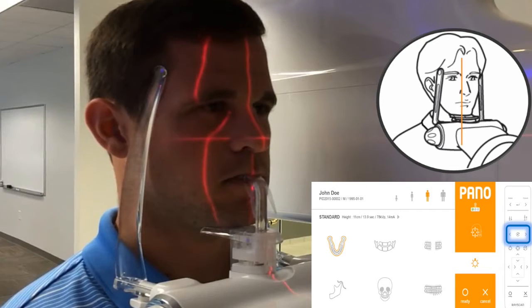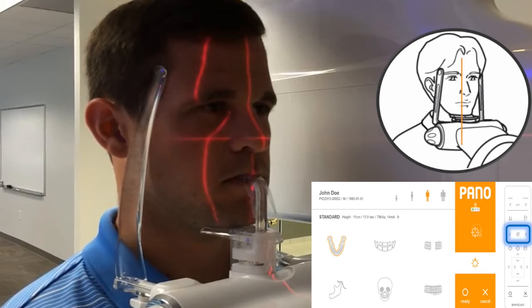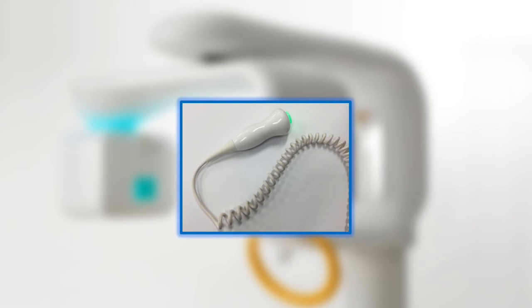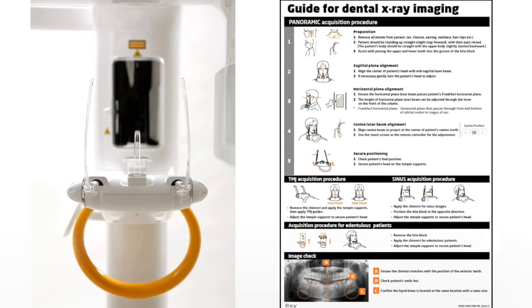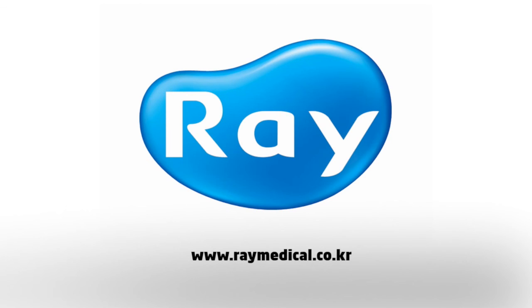Carefully adjust the head supports so that they gently but firmly grip the patient's head. Ask the patient to maintain a firm grip on the hand grips and step forward slightly. This position makes them slightly off balance and hanging onto the support handle, forcing them to stretch their neck as far as possible, which decreases the spinal shadow on the anterior regions. Ask the patient to press their lips together and press their tongue against the roof of the mouth. Closing their eyes will help them remain still. Move at least 7 feet away from the unit and protect yourself from radiation. Press and hold down the exposure button for the duration of the exposure. For edentulous or partially edentulous patients, be sure to use the appropriate positioning device. For more information on proper positioning and usage of RayScan Alpha Plus, please consult the positioning guide. Thank you for watching how to take panoramic images with RayScan Alpha Plus.